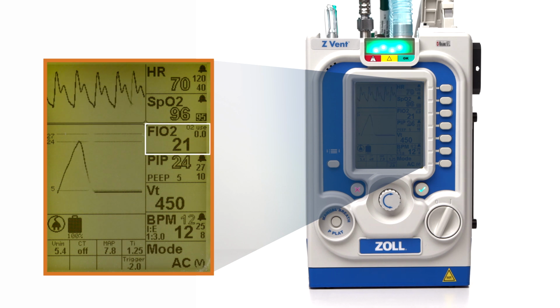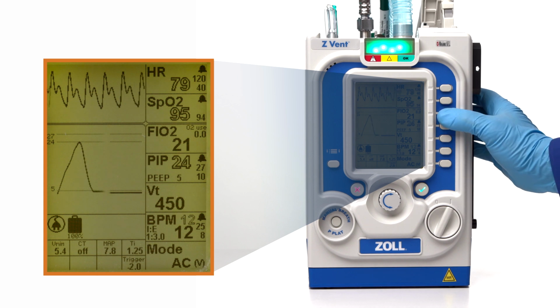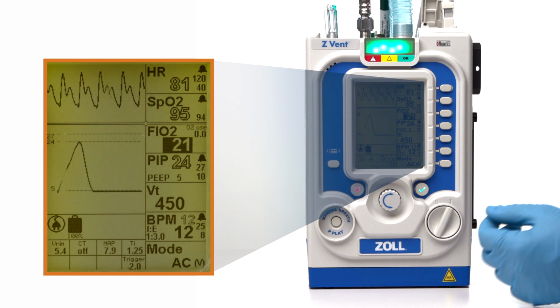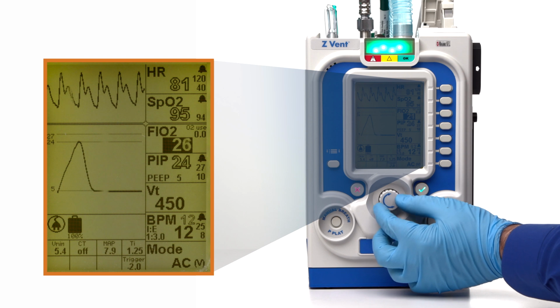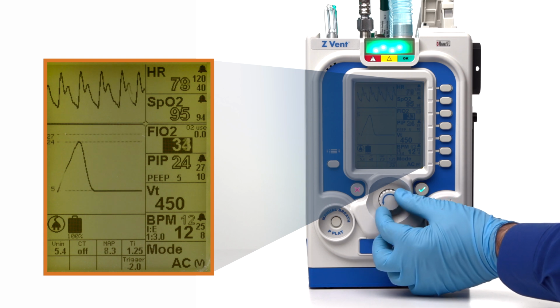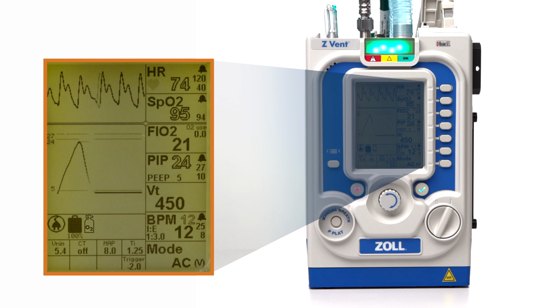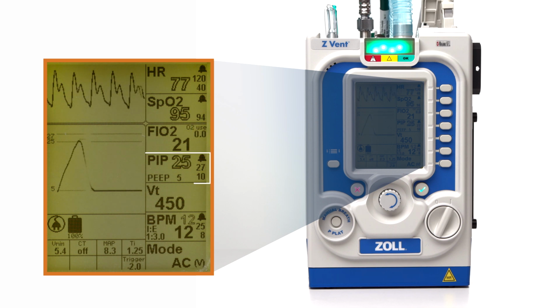The third window is fraction of inspired oxygen percentage, or FiO2. The desired FiO2 can be adjusted in 1% increments from 21 to 100%. Press the parameter button once to change the desired FiO2 level. When the Z Vent is used with high pressure oxygen, the current oxygen liter per minute usage is displayed in this parameter window. The fourth window is peak inspiratory pressure, or PIP.